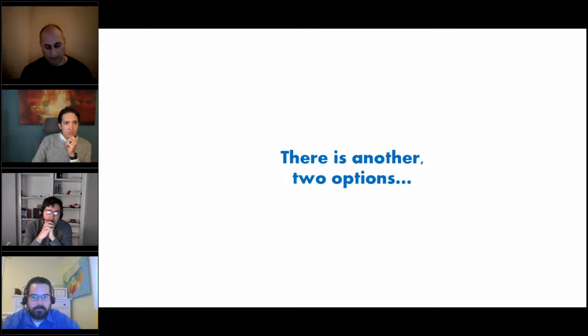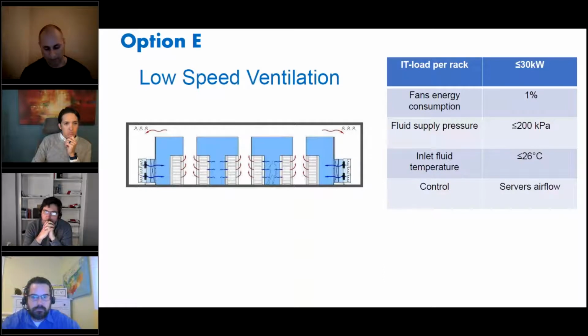But there are another two options which I want to describe to you now. Low speed ventilation. It's a solution which supplies air in the amount the servers need, and it fully satisfies all kinds of servers and gives us the possibility to work even with high temperature air, because there is no mixed air from the hot and cold corridor.